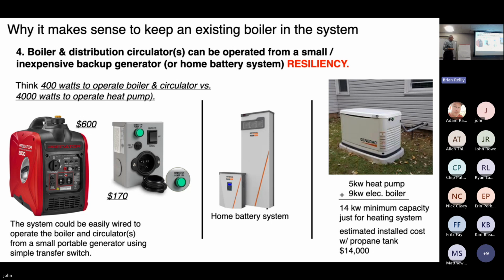Here's another thing, resiliency. I could run a gas boiler or even an oil boiler on a little, I call them tabletop generators like this, or little camping generators that Harbor Freight sells for $600. Honda's a little more, Honda's about $1,000. But here's an idea. When you add the heat pump to the system, or even when you just install a fossil fuel boiler system, you can use a transfer switch to set up all the electrical feed into the boiler and the distribution system. If you're in a power outage and you've got one of these and you've got a few gallons of gasoline to run it for a few days, all you have to do is flip the transfer switch, and now you've got the boiler and the zone circulator or the zone valves all operating. You could operate a residential hydronic system, an average one, probably on less than 500 watts. And this is a 2,000 watt generator.